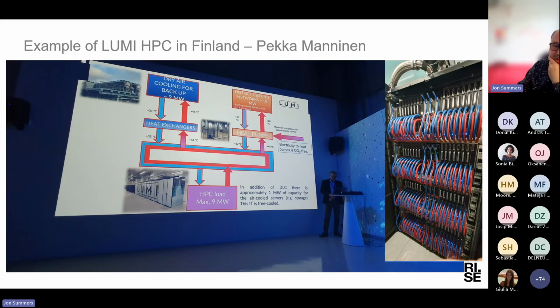They can either reject the heat straight through heat exchangers to dry coolers outside, at low overhead since they're not using compressors, or they can push it through the heat pump and distribute it to the district heating.